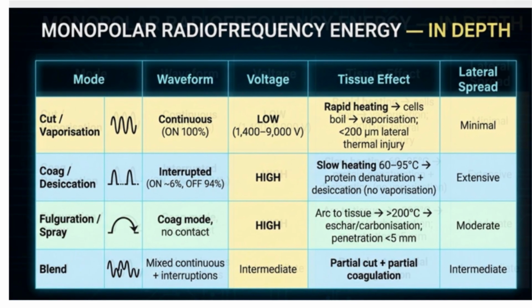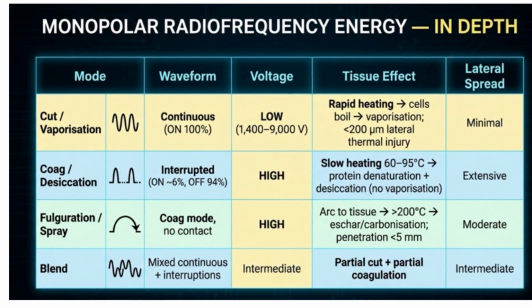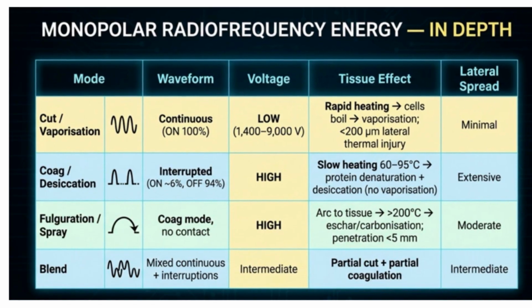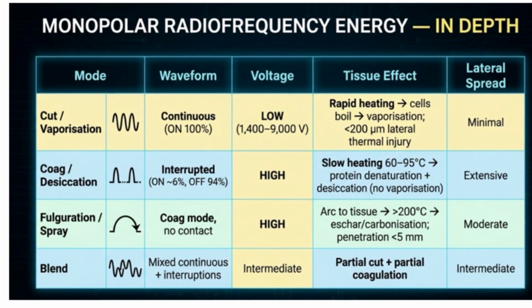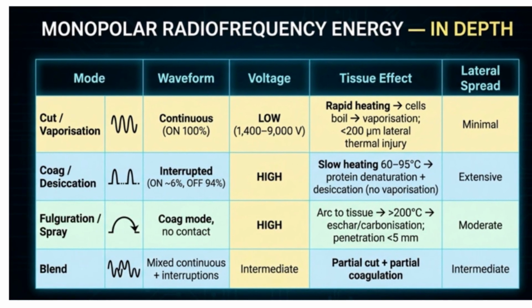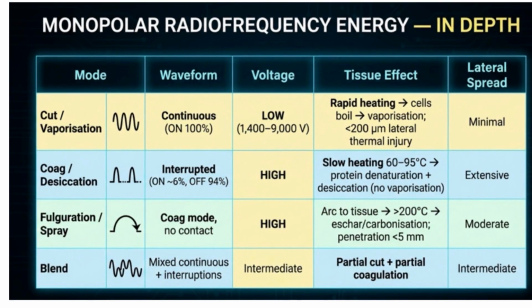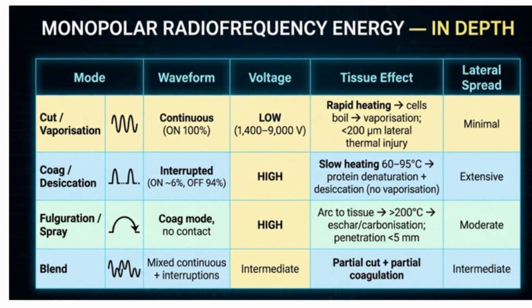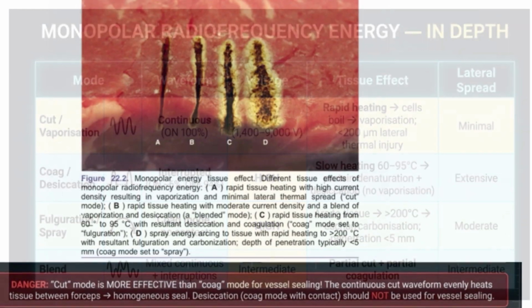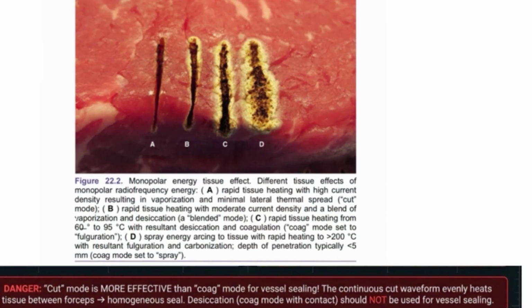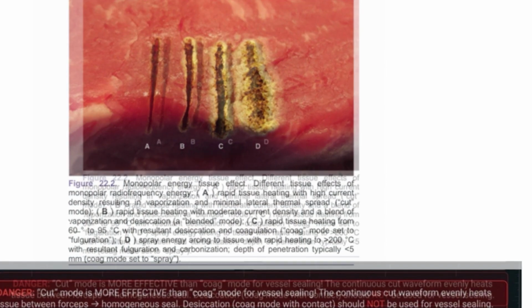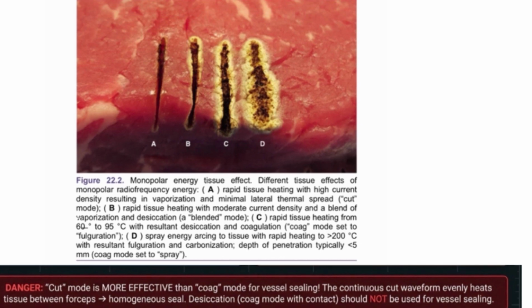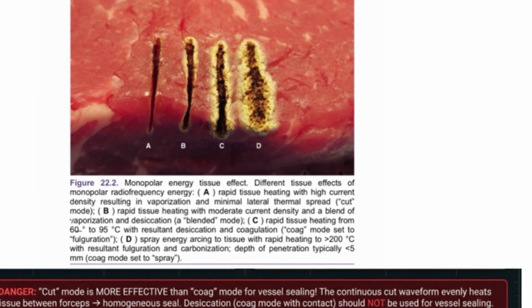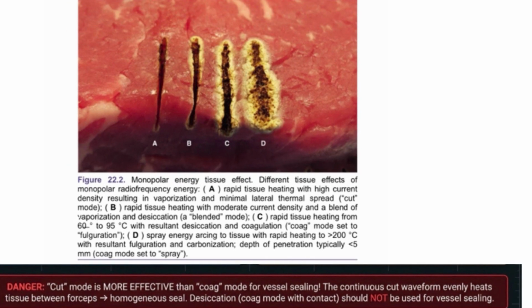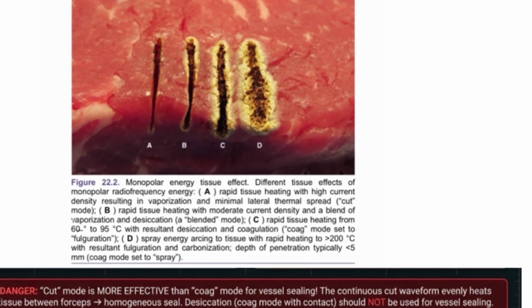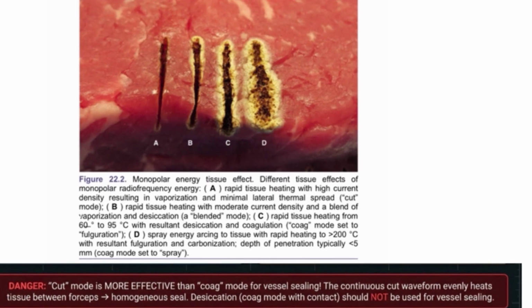The blend mode, mixed continuous plus interrupted flow of current is there. The voltage used is intermediate. It is partial cut plus coagulation. The lateral spread is intermediate. The image shows monopolar energy effect on the tissues. The first is the cutting, the second is the blended, the third is the coag, and the fourth is the spray mode. Cut mode is more effective than coagulation mode for vessel sealing.